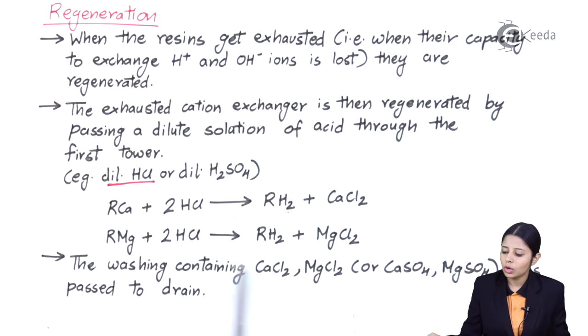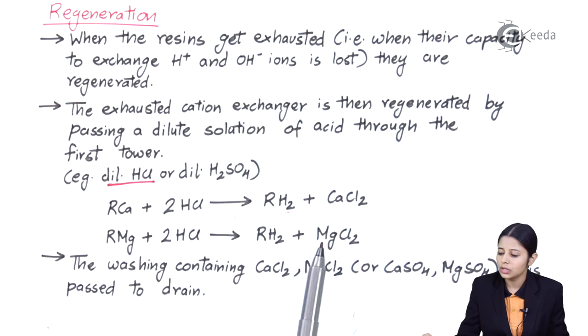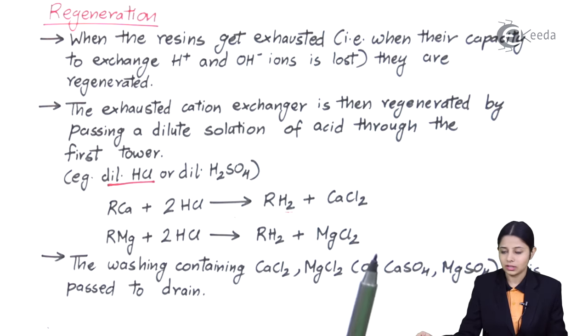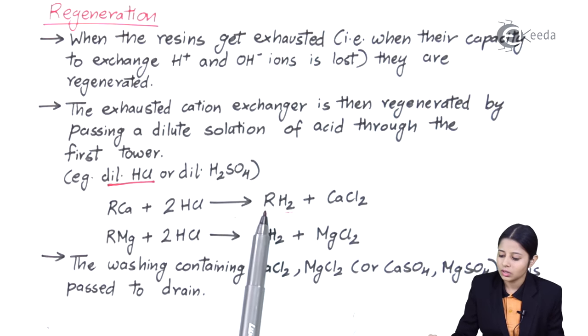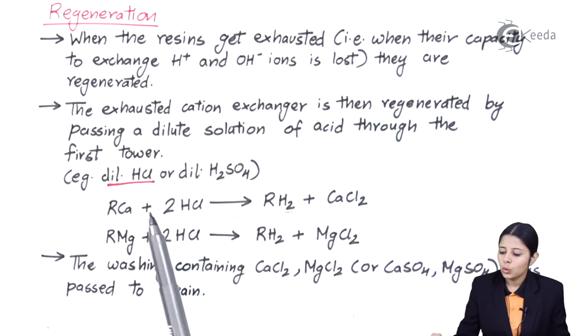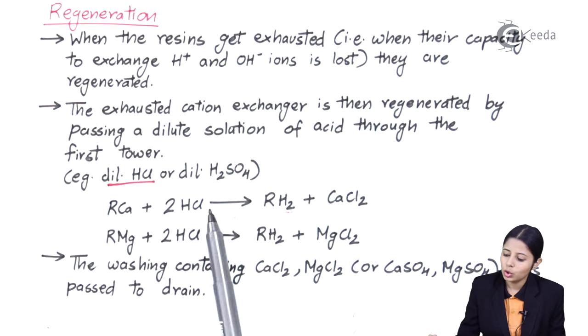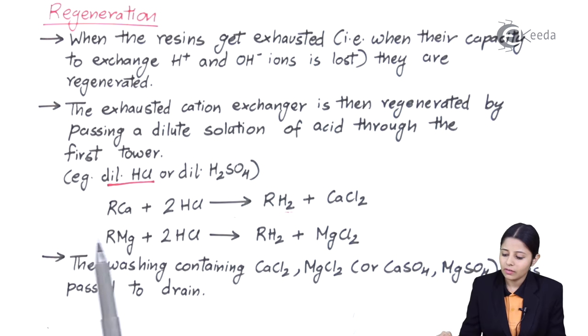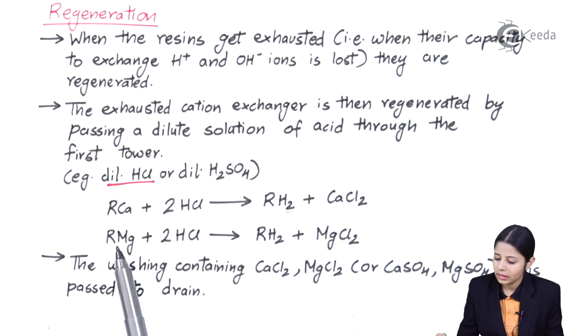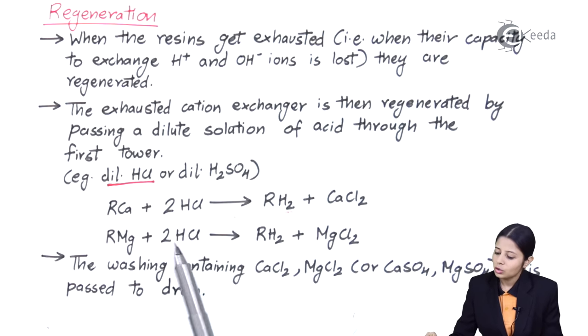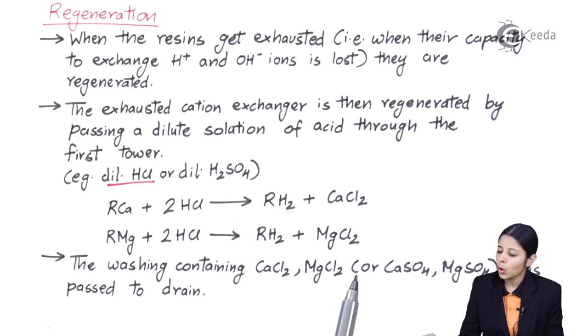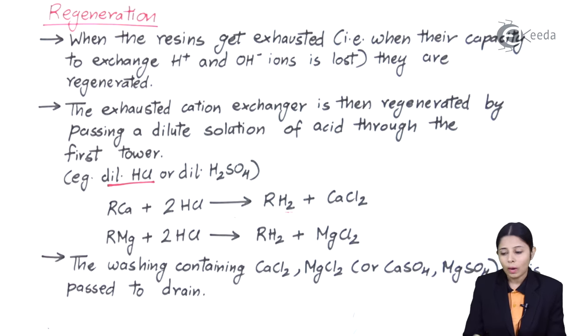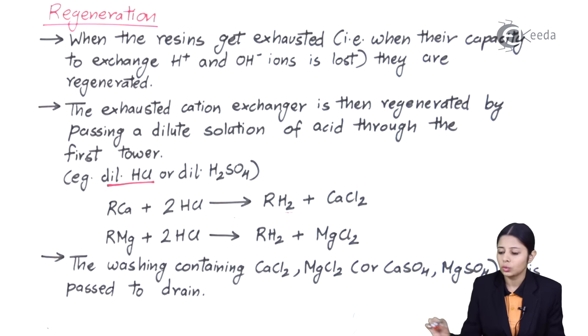Similarly, RMg + 2HCl → RH₂ + MgCl₂. Checking the balance of RCa + 2HCl → RH₂ + CaCl₂: 1R each side, 1 Ca each side, 2H and 2Cl on each side — balanced. For RMg + 2HCl → RH₂ + MgCl₂: 1R each side, 1 Mg each side, 2H and 2Cl on each side — balanced. The washings containing CaCl₂, MgCl₂, CaSO₄, MgSO₄, etc. are passed to drain, as they are byproducts. Only the regenerated RH₂ resin is needed.